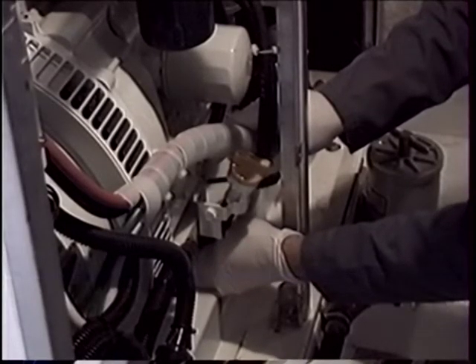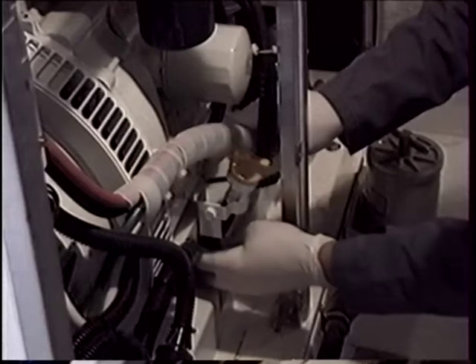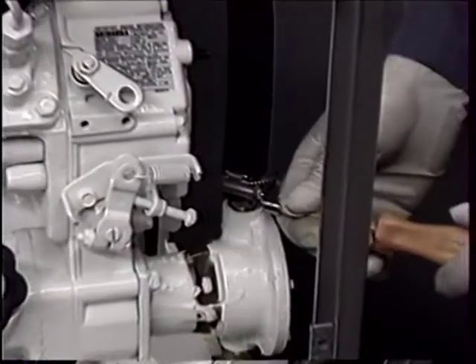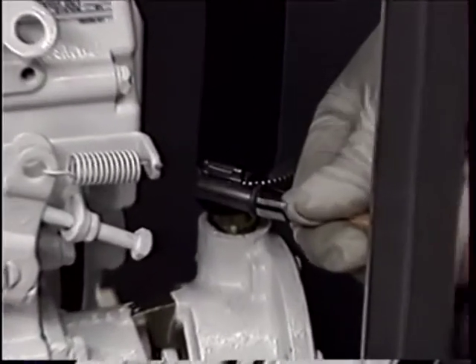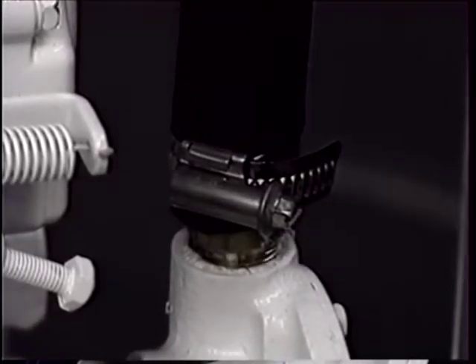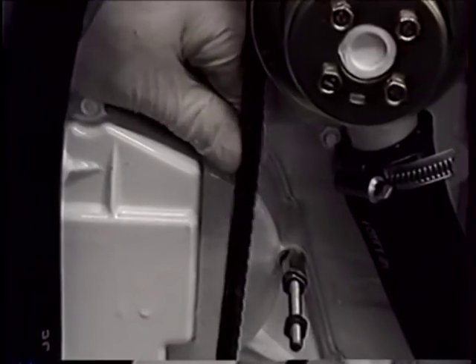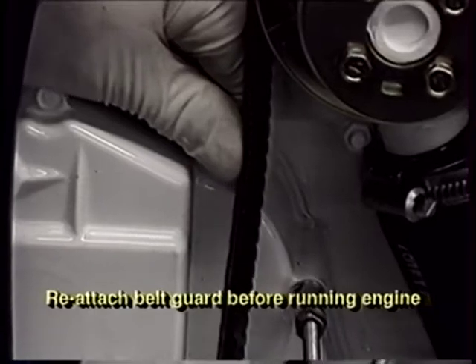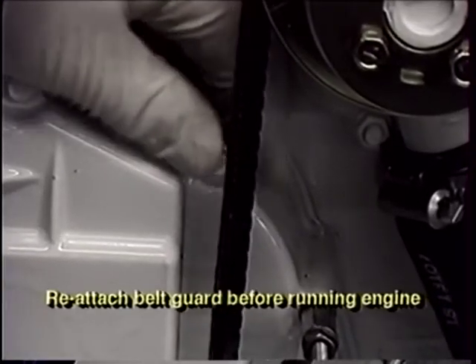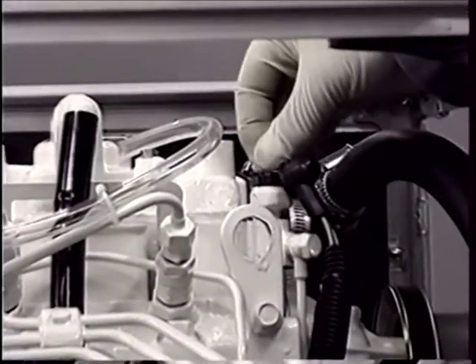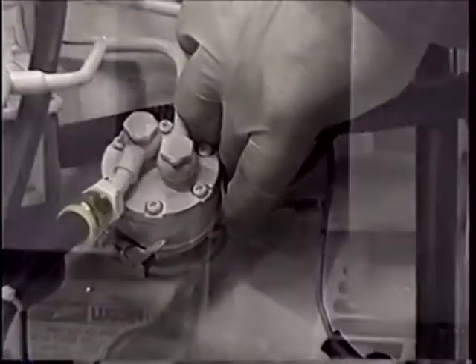Inspect the base pan below the unit for any signs of fluid, which may indicate a possible leak. Use a screwdriver to check all of the unit's hose clamps for tightness. Inspect the drive belt for correct tension and wear. The drive belt should give no more than ½ an inch. Check for loose or chafing wires.